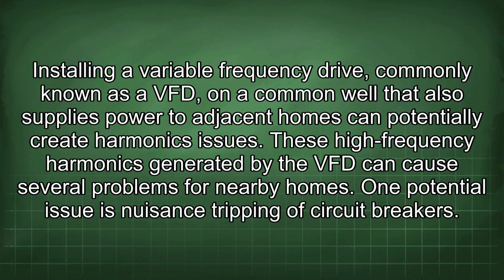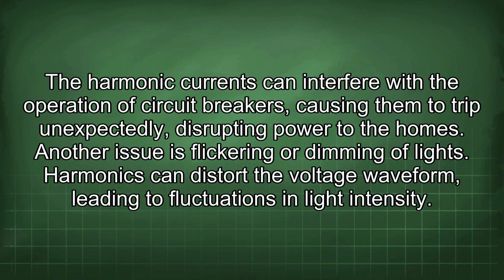Installing a variable frequency drive, commonly known as a VFD, on a common well that also supplies power to adjacent homes can potentially create harmonics issues. These high-frequency harmonics generated by the VFD can cause several problems for nearby homes. One potential issue is nuisance tripping of circuit breakers.